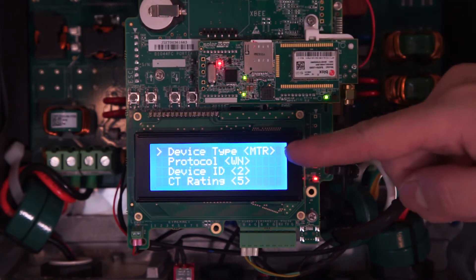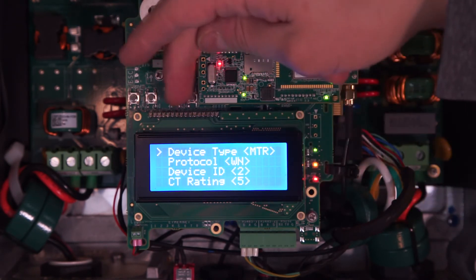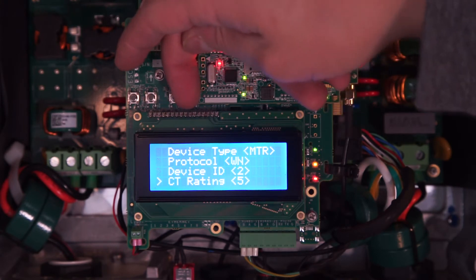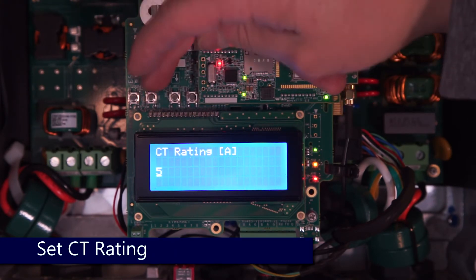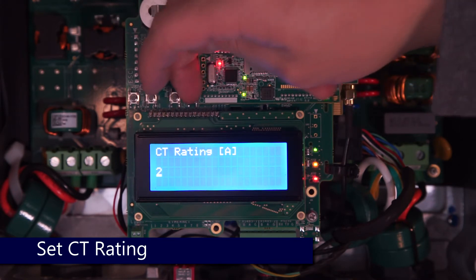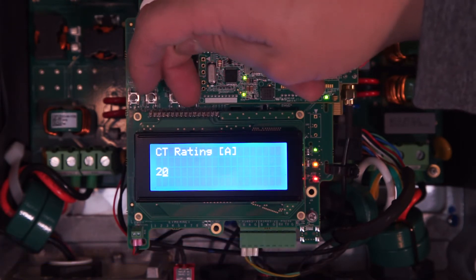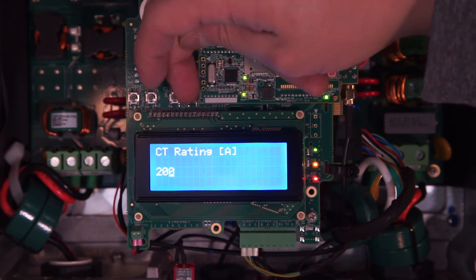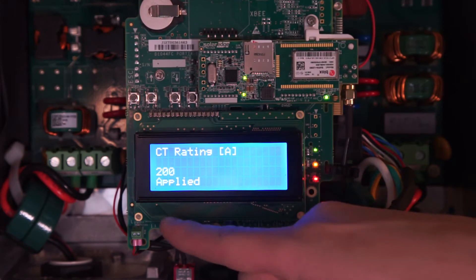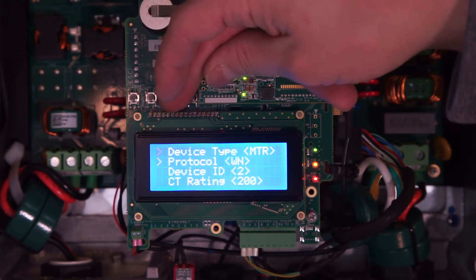We can see that our meter is communicating because the CT rating has changed from 0 to 5. We'll need to set the CT rating based on the labels on our CTs — in this case we've got a 200-amp CT. So we'll use the down arrow to change that 5 to 2 and input 200. Enter moves you forward, escape moves you back, and a long hold on enter to confirm. Our CT rating is set.